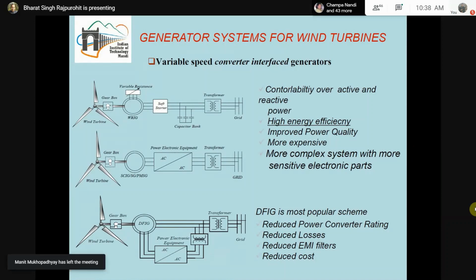So the wound rotor induction generator, as electrical engineers we are aware, is an induction machine having rotor terminals available to us. The rotor is not a short circuit rotor; it has a winding, and through a slip ring mechanism the terminals are brought out, and the speed can be controlled by providing a variable resistance in the rotor circuit. So this is a very simple scheme. By providing this, a variable speed system can be made, the speed can be controlled, and hence we are able to capture more energy from this scheme. This is an additional scheme to what we discussed in the previous slide, known as the squirrel cage induction generator. Now see the middle figure here.